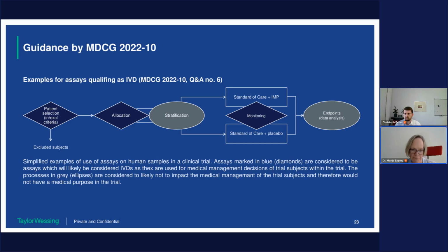The stratification of patients and the statistical analysis, the data analysis, in order to see whether endpoints have been reached, would not be considered as having a medical purpose, so would not be considered as an IVD. But patient selection, this is what a companion diagnostic typically does, the allocation of patients to different groups, and also the monitoring during the treatment in the clinical trial, the assays used for these purposes would qualify as IVD.